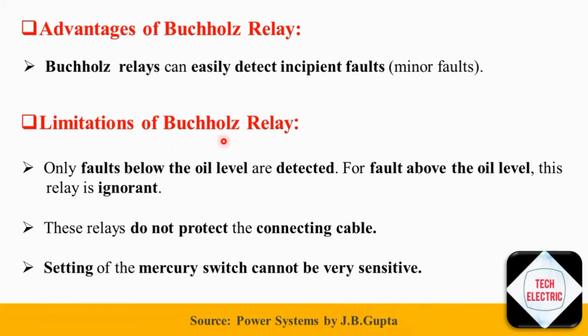But there are also limitations of Buchholz relay. Only faults below the oil level are detected. For faults above the oil level, this relay is ignorant. Another limitation of Buchholz relay is that it does not protect the connecting cable. As I already told you, Buchholz relay only provides protection for the internal fault, so it does not protect the connecting cable. Therefore, a different protective system is required for that purpose. Another limitation is that the setting of the mercury switch cannot be very sensitive. If mercury switches are made very sensitive, then there can be a false operation by vibrations, earthquakes, mechanical shocks to the pipe, swinging of birds, etc.